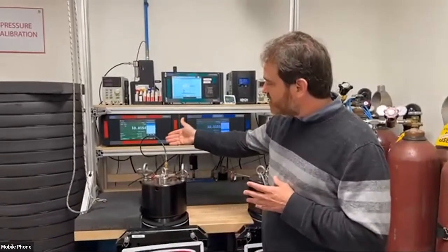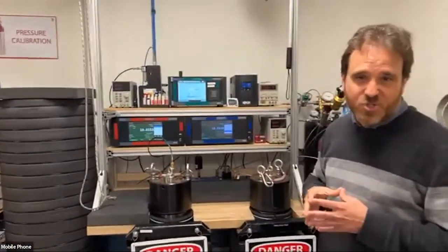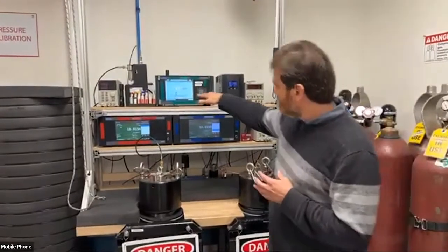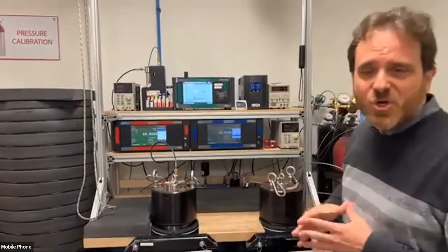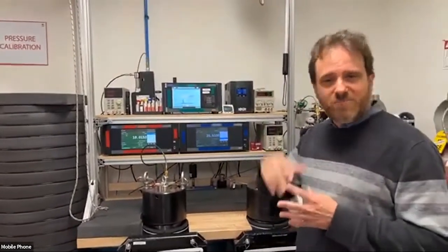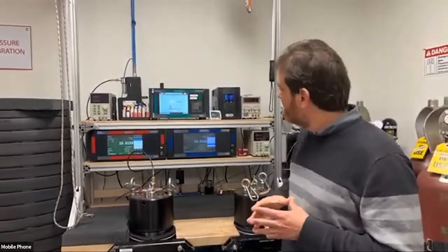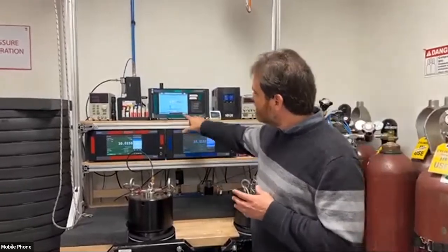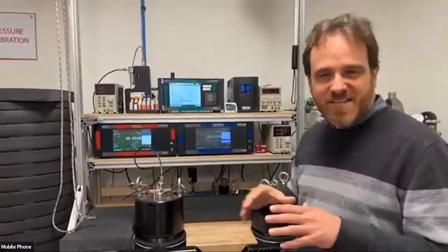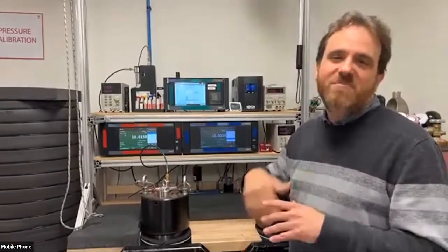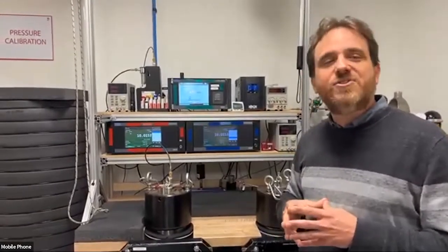This is color coded, so this green hose means it is actually running the CPC 6000 pressure controller at the moment. And right now, it's at basically 1 ATM. So it might be just starting off the complete pressure cycle. So we always start off at 1 ATM, or it might be finishing the pressure cycle. Based on this reading here, I can see that we're actually starting the pressure cycle for this unit. So there is a stabilization period at 1 ATM, and then we start actually pressurizing at the other levels.